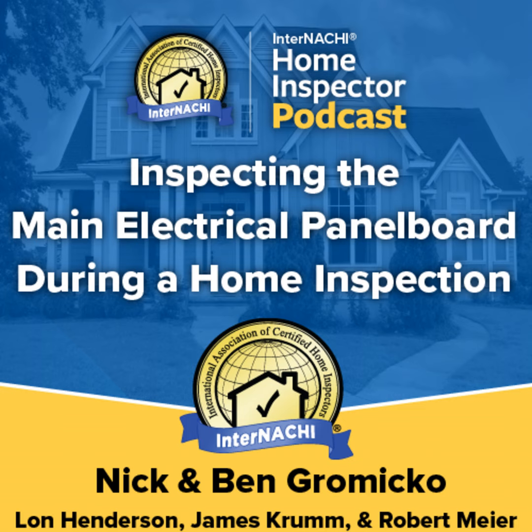Split bus panel. Between the 1950s and mid-1980s, split bus panels were installed in many homes. These panels do not have a main breaker or one main disconnect. They have two bus sections. Typically, the upper bus has double-pole 240-volt breakers, including one that feeds the lower bus section where the majority of 120-volt breakers are installed. The upper bus section should not have more than 6 separate breakers or breaker handles.